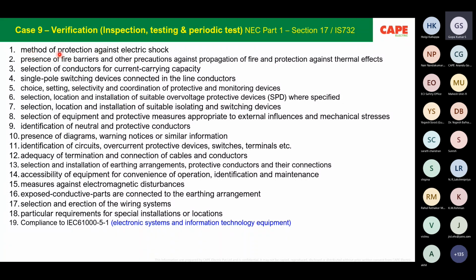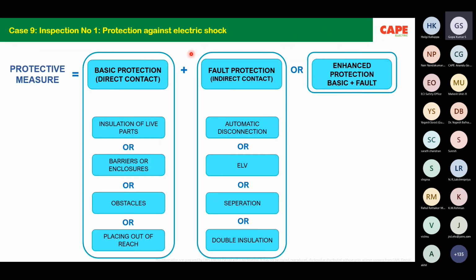Now I will explain only the first one, protection against electric shock. Protection against electric shock consists of basic protection and fault protection. There are several methods possible in a circuit. For example, insulation of live parts, barriers or enclosures, obstacles, placing out of reach. These are the basic protective measures. Fault protection: fault is a condition. Once the basic insulation has failed, you go into a fault situation. So fault protection is achieved by these measures: automatic disconnection, extra low voltage separation, double insulation.